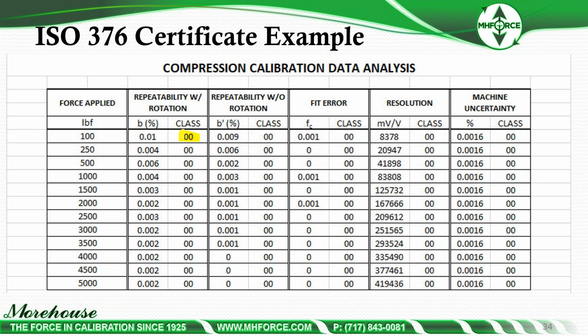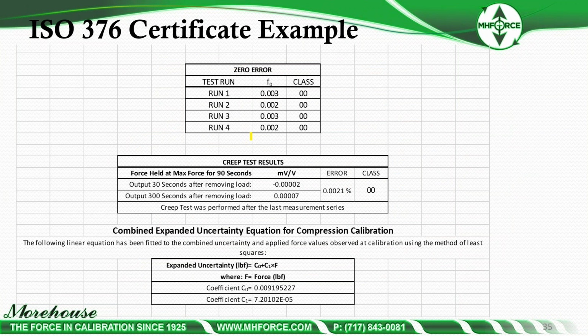If I had a better example with a class half here and then class 00 here, you'd see that I may be able to use this cell from 5% to 100% at class 00. So there's a bigger picture of all the uncertainty. And then there's the zero, the creep results, and then more on this expanded uncertainty equation. So you can use this equation. If you want to know what the uncertainty is at 300 pounds, and this is a 5,000 pound device, you can use this equation. And then we get to the point of reporting.